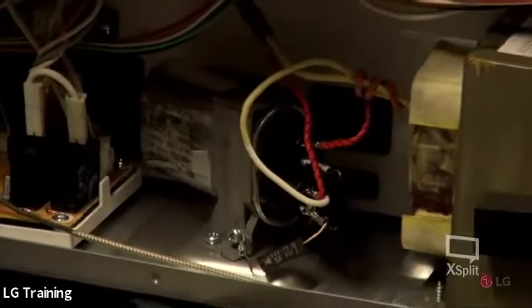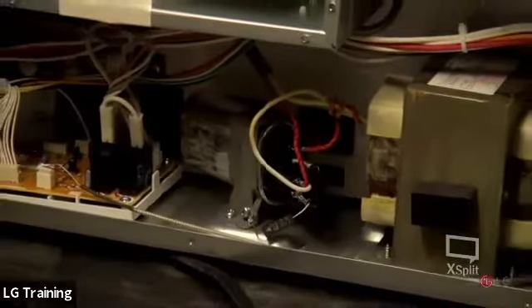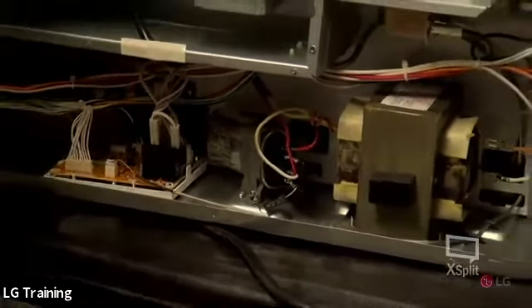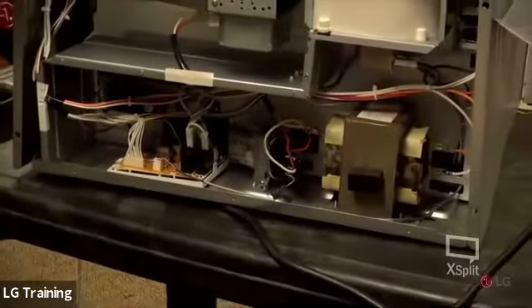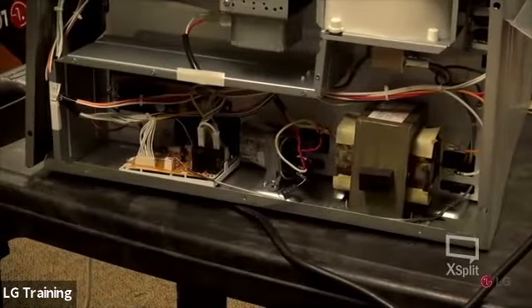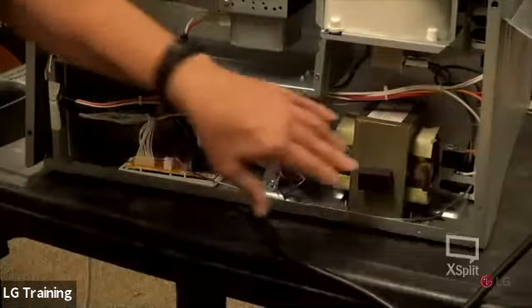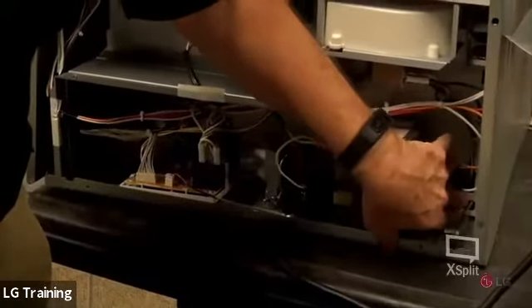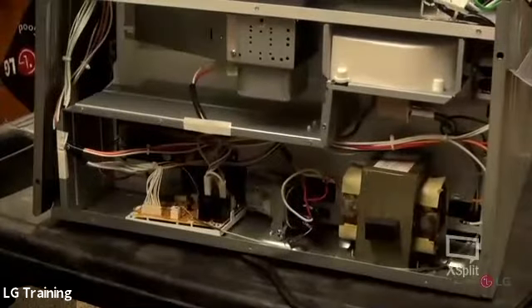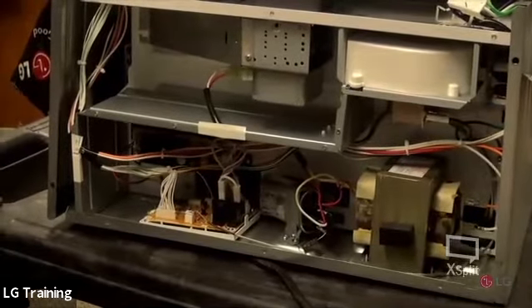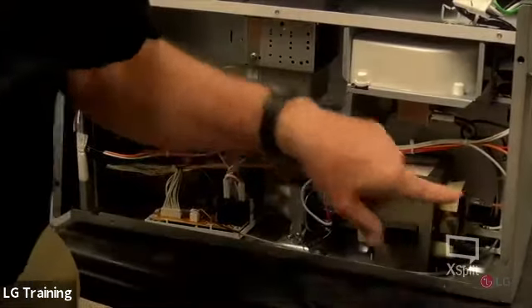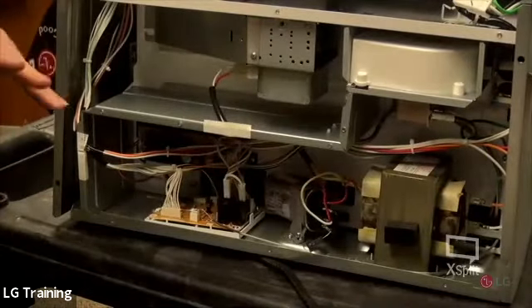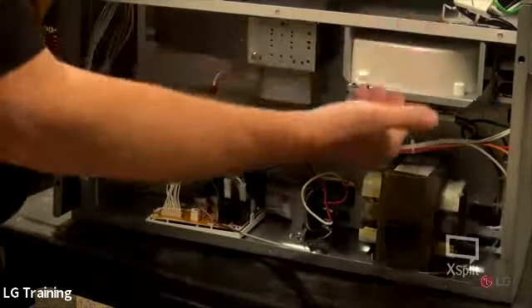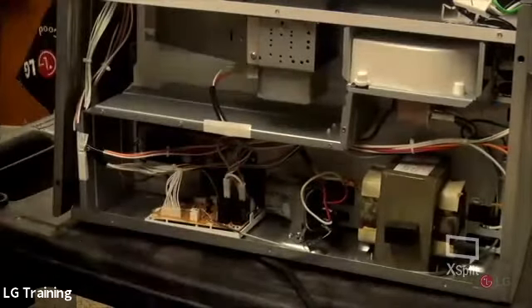On your high voltage transformer, there's really only one voltage check worth doing. This is the way I was taught decades ago: I always look for the primary side of the transformer to see if I've got line voltage there, and that tells me where to go. So I put meter leads with alligator clips, set the control panel for about 10 or 15 seconds, power it up, and look for that 120 volts. It gives me a starting point, telling me whether my problem is here or there, depending on whether I have voltage.